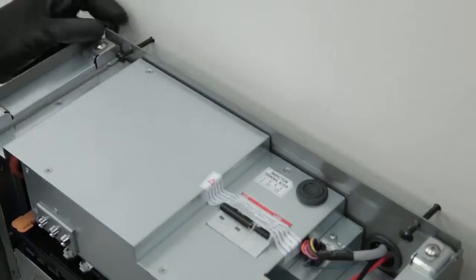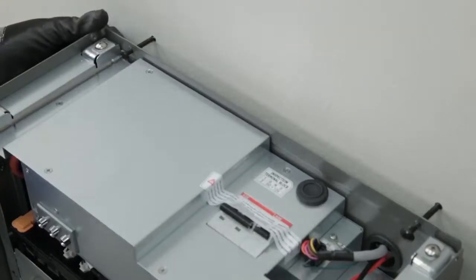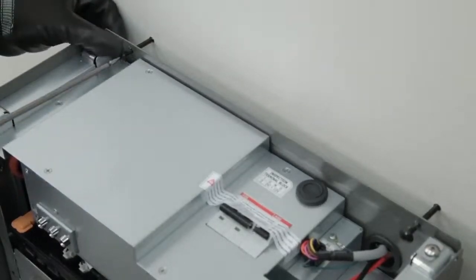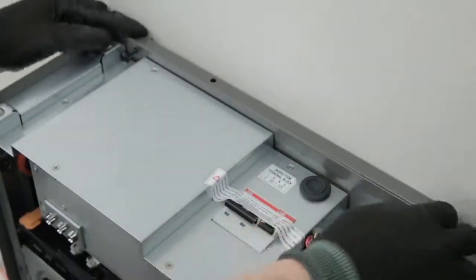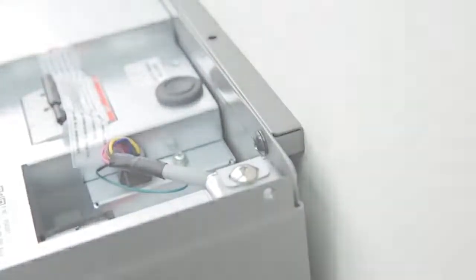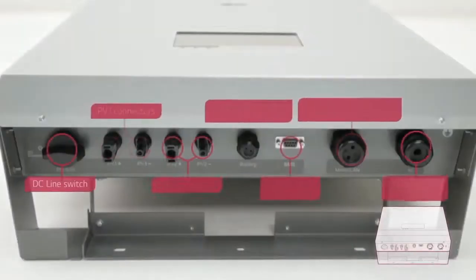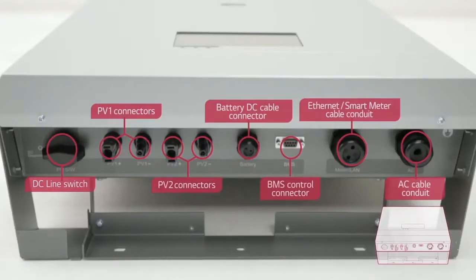Screw the bolts into the holes only down to the halfway through the screw holes on the battery. Place the bracket by simply dropping it on the screws between the wall and the battery. Now, tighten up the screws all the way. Now we will look into how to connect the cables from the PCS to the battery, PV array, and power grid. If you have a look at the bottom of the PCS, you will find several connectors and a series of conduits.